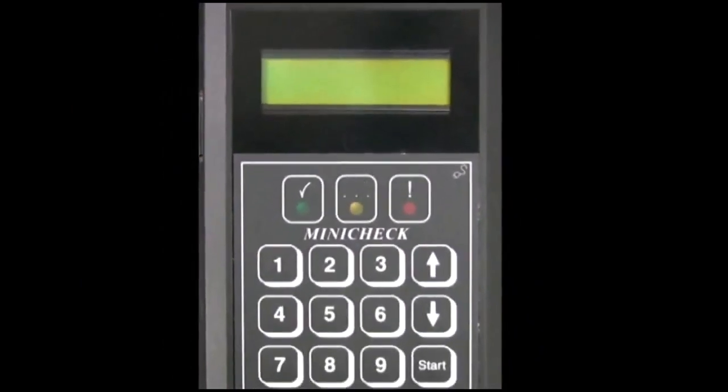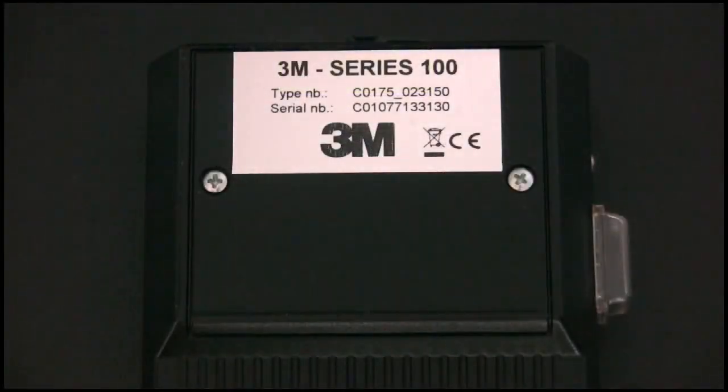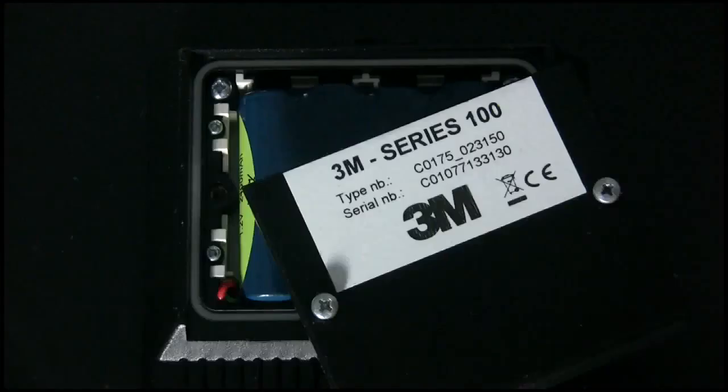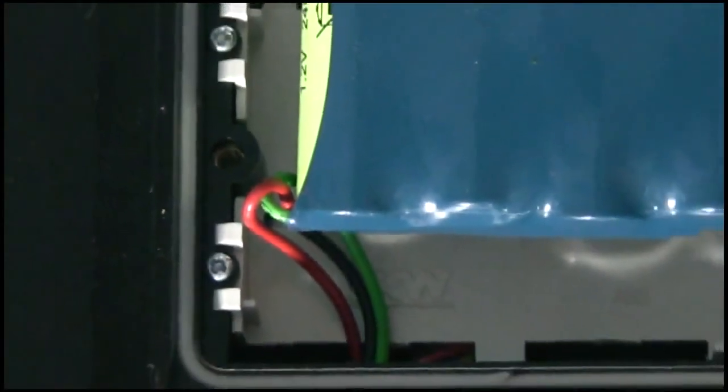The battery typically lasts 2 years. The battery can be accessed and replaced via removing the battery panel on the back of the device. Because of the complexity of the wiring involved, it's recommended to contact 3M Purification technical support to complete the task of battery pack replacement.